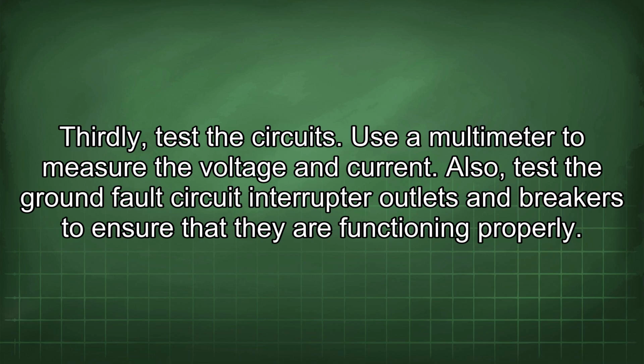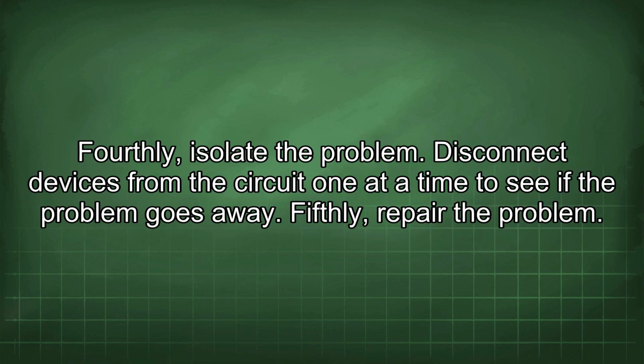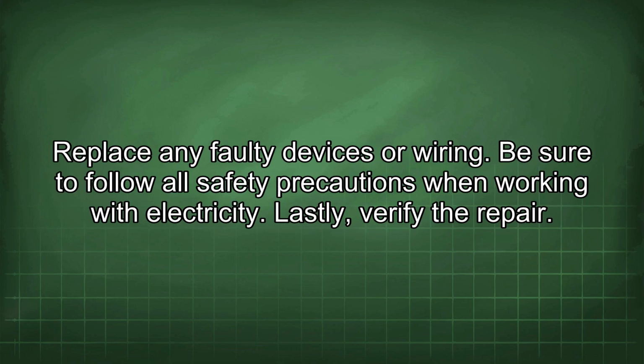Also, test the ground fault circuit interrupter outlets and breakers to ensure that they are functioning properly. Fourthly, isolate the problem. Disconnect devices from the circuit one at a time to see if the problem goes away. Fifthly, repair the problem. Replace any faulty devices or wiring. Be sure to follow all safety precautions when working with electricity.